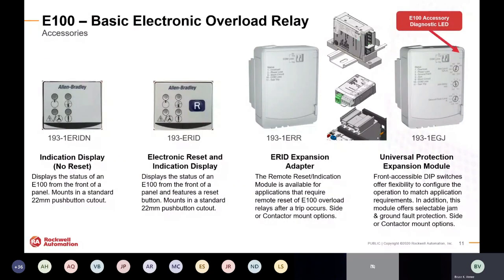If we look a little closer at some of the more advanced accessories for the E100, we have the same 193 ERID, which is an accessory for the E1 Plus today. That's not going away—it just went through a series change where we changed the way it looks cosmetically so it fits within the same portfolio of the E100. Essentially this device is an electronic method to reset the overload, and it also gives you LED indicators for the overload status. So without having to open the door to get to the actual component, you can see the status of the overload using this component mounted on the front of the door.